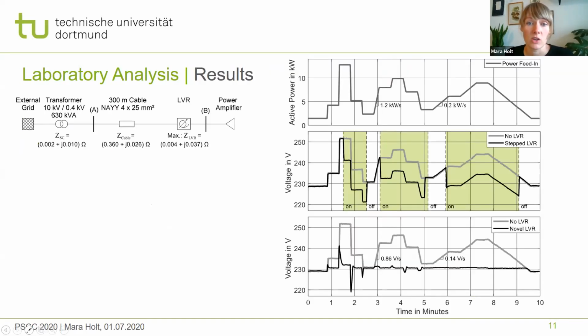This slide depicts the measurements at busbar B. Here you can see the single-phase power feed-in and the resulting voltages of the different setups. In the reference setup, the voltage signal at busbar B tracks the power signal. With the usage of a line voltage regulator, the voltage rise at busbar B should be compensated. The stepped line voltage regulator can reduce the line voltage by 10 volt. It switches on at 236 volt and switches off at 225 volt with a delay of 10 seconds. With this mechanism, the mean voltage decreases. Nevertheless, the on-off control of this line voltage regulator amplifies the voltage fluctuation and emits additional flicker.